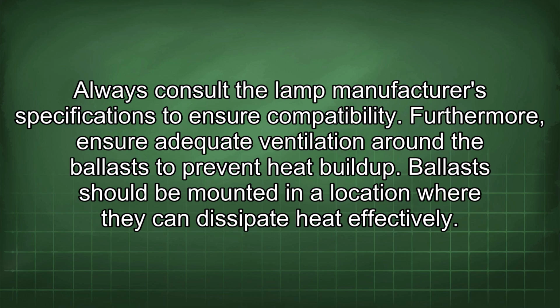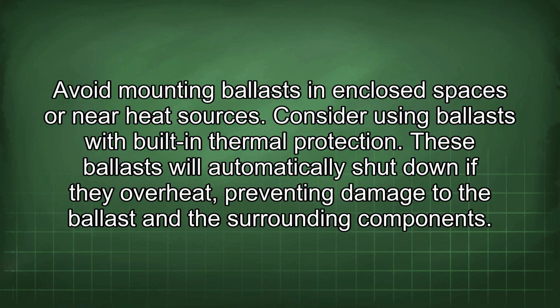Furthermore, ensure adequate ventilation around the ballasts to prevent heat buildup. Ballasts should be mounted in a location where they can dissipate heat effectively. Avoid mounting ballasts in enclosed spaces or near heat sources. Consider using ballasts with built-in thermal protection. These ballasts will automatically shut down if they overheat, preventing damage to the ballast and the surrounding components.